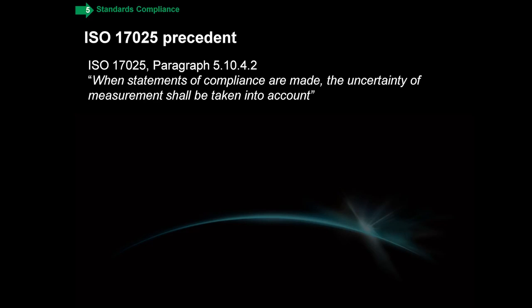One of the critical paragraphs in 17025 is 5.10.4.2, which says: when statements of compliance are made, the uncertainty of measurement shall be taken into account.